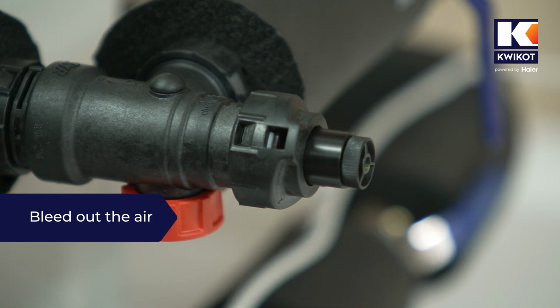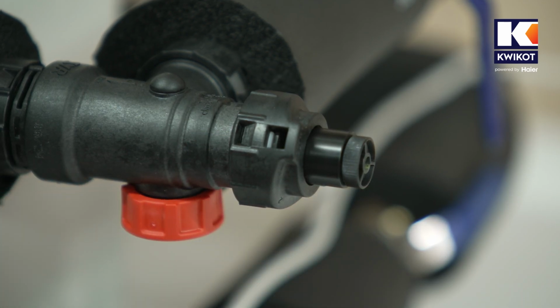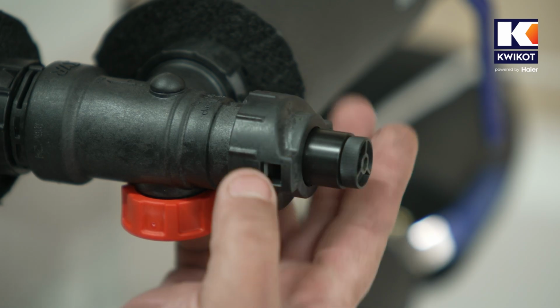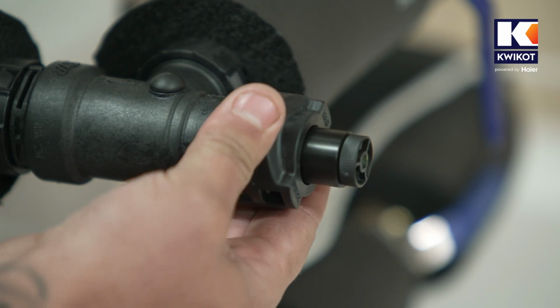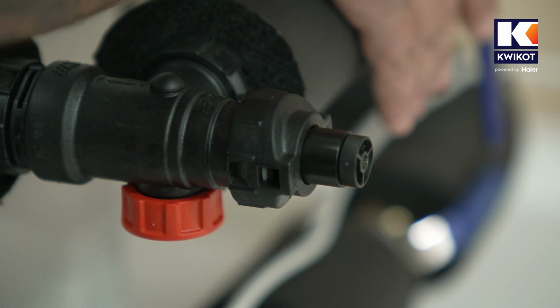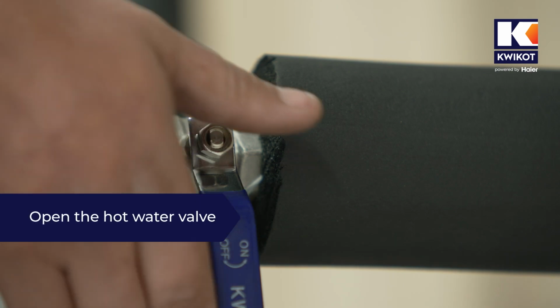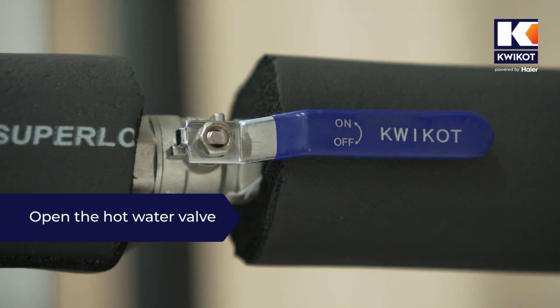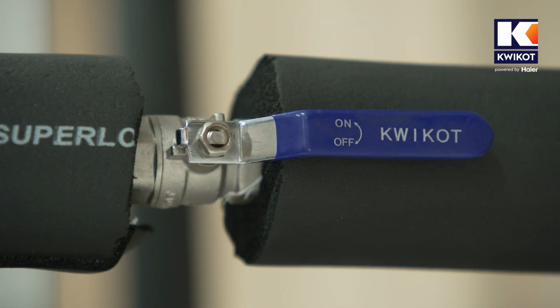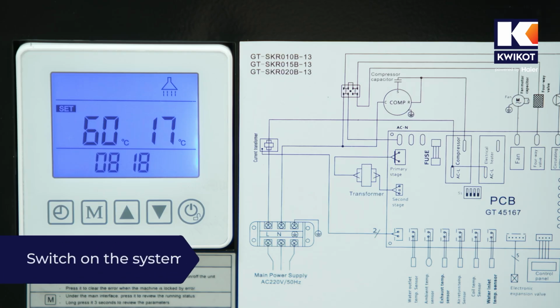and bleed all the air out. Once the water is running clear through the system, you can close this valve again. And then we open the hot water ball valve leading back to the water heater. And now your system is full of water, so we can switch on the system. To do that, we switch on the heat pump on the control panel.